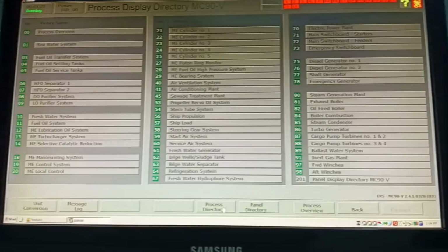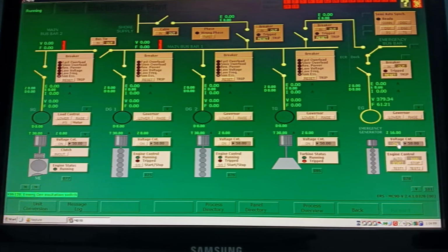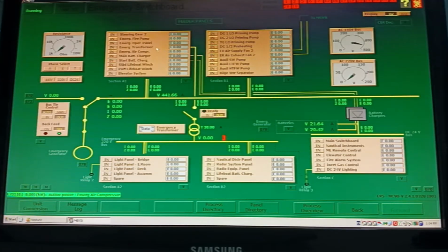Okay, once the RPM reaches 1800, we need to go to our electric power plant and turn on the voltage excitation and connect the breaker. And then we have to go to our emergency bus bar and to our emergency switchboard, and we have to switch on every emergency equipment. Give supply to every emergency equipment. Switch on the transformer. Above is 440 volts, below this is 220 volts.